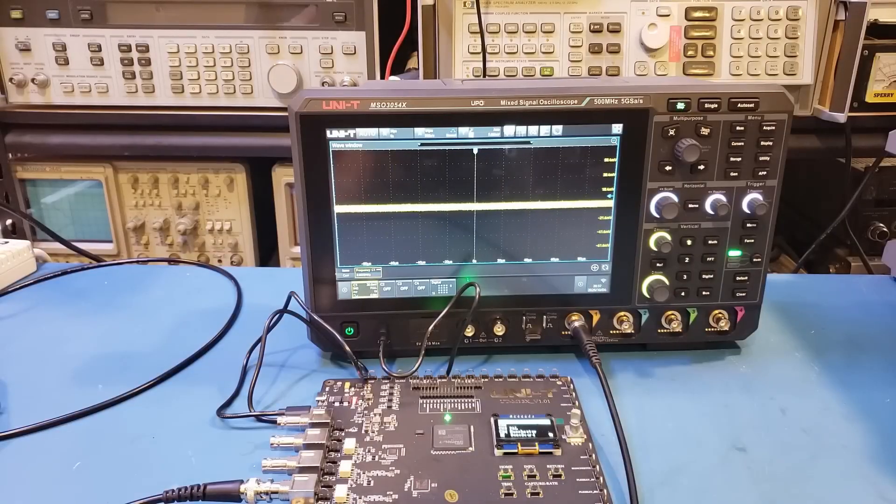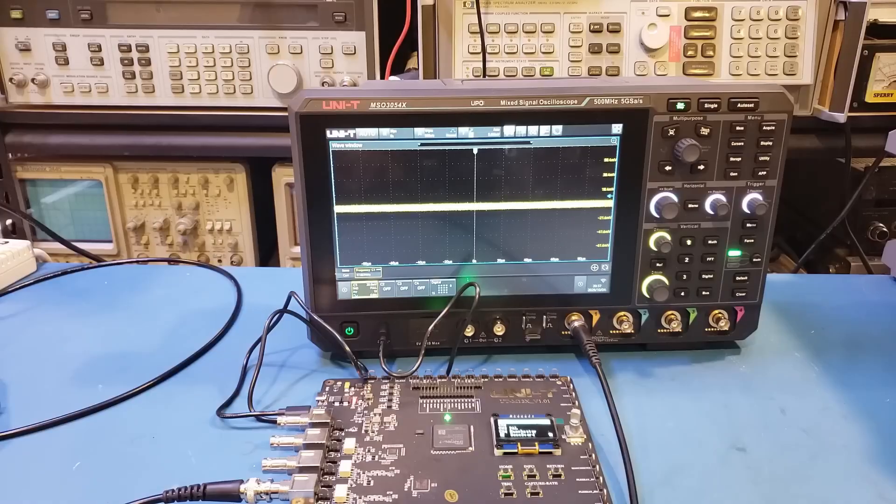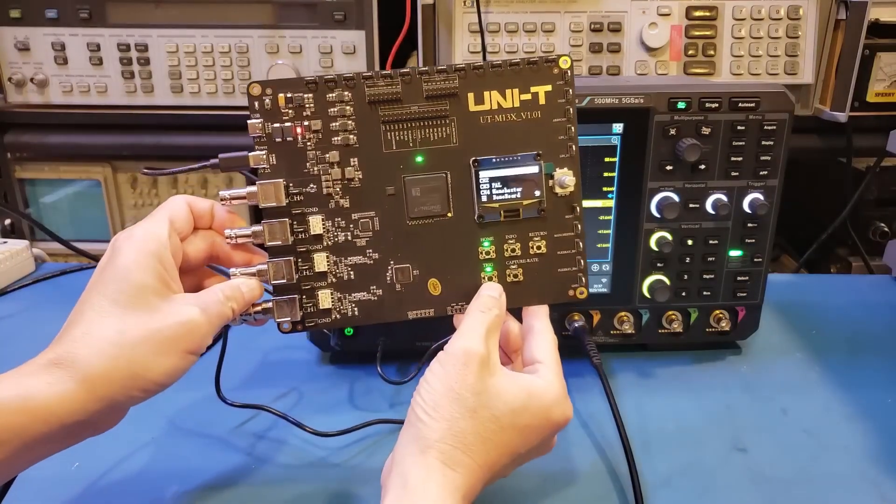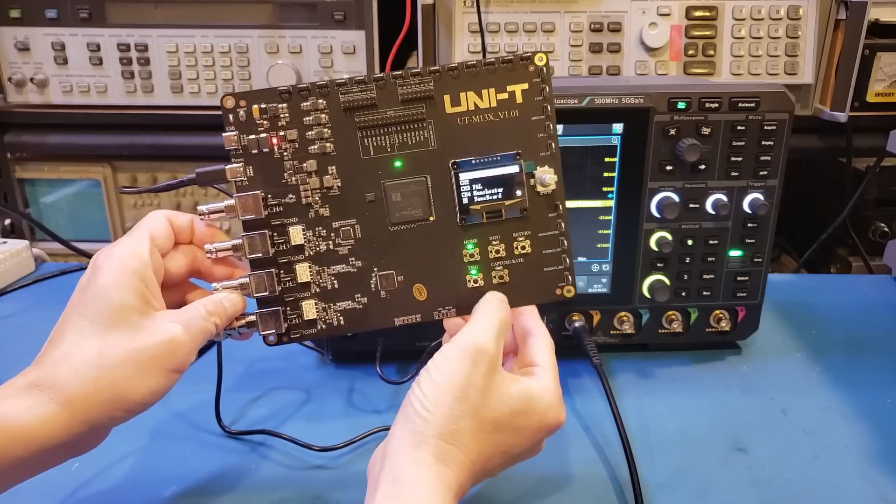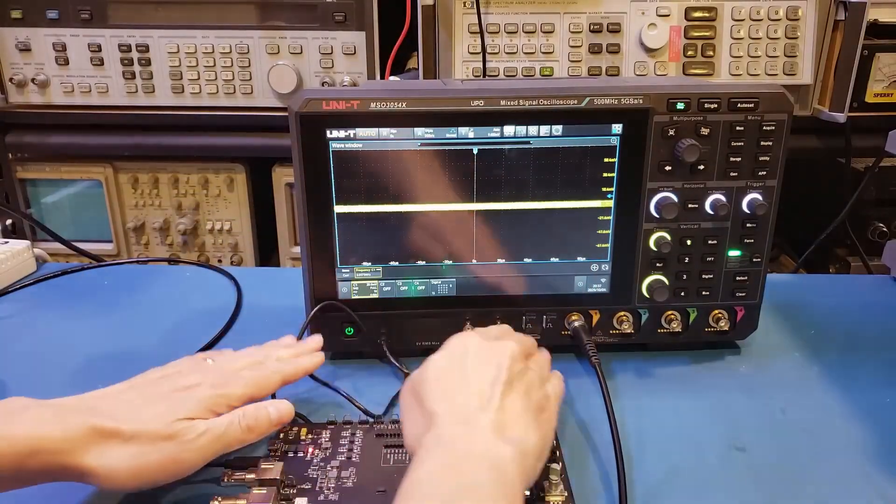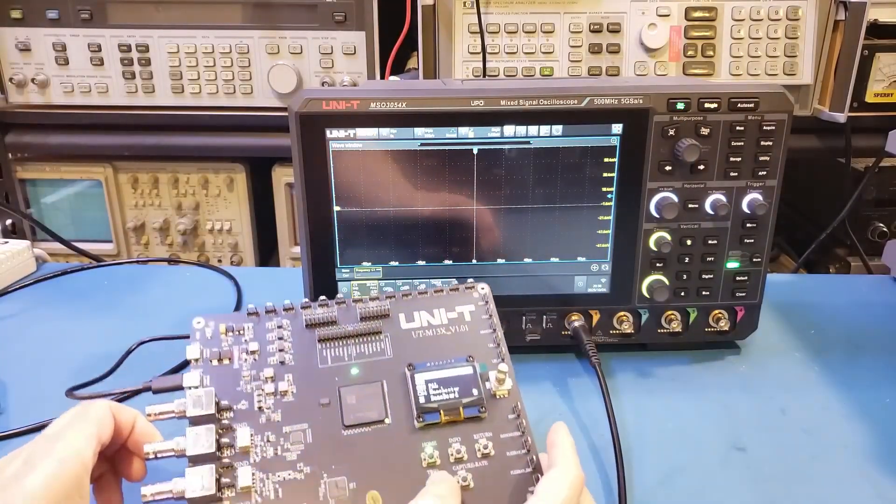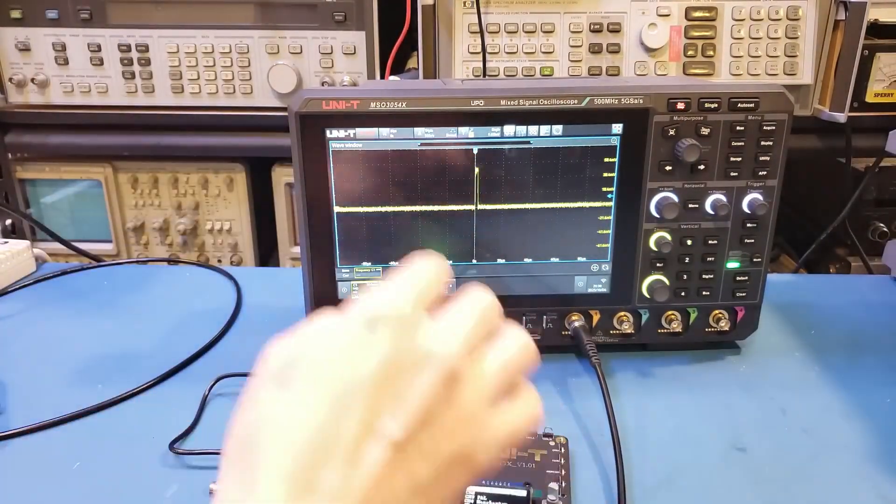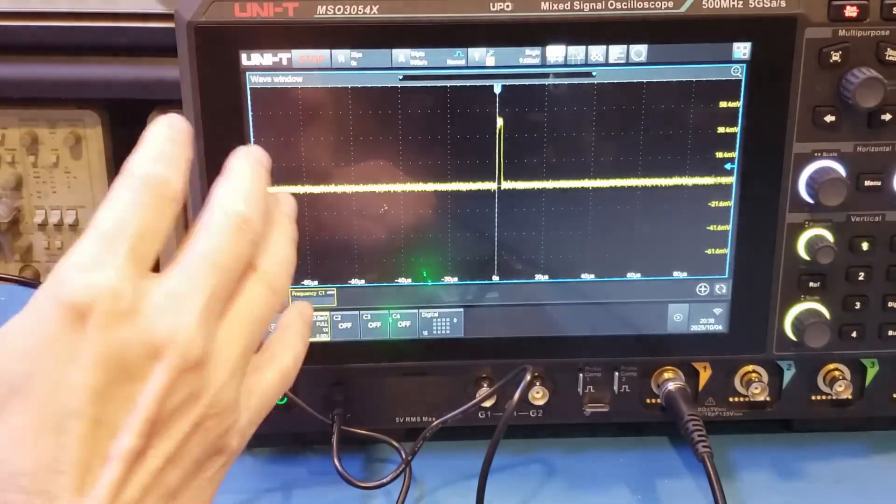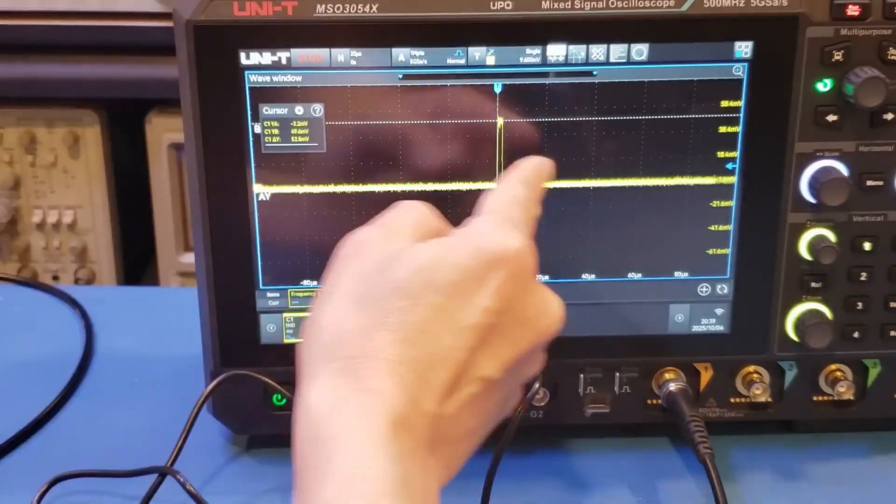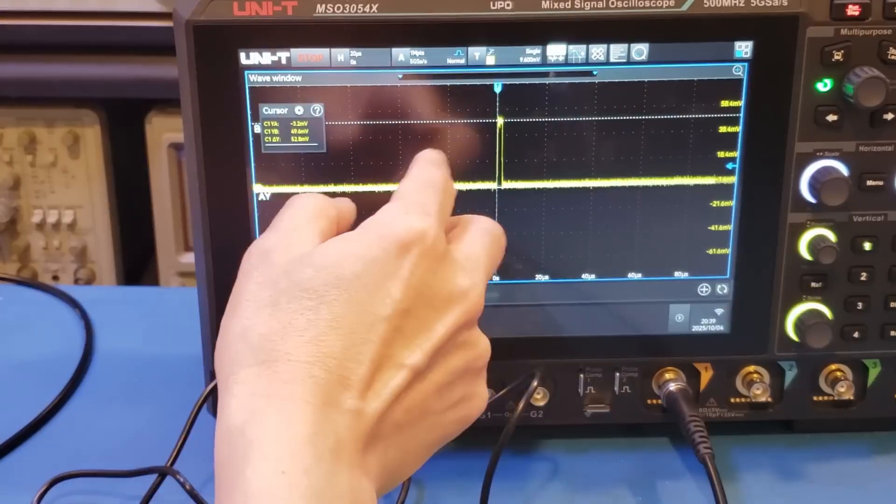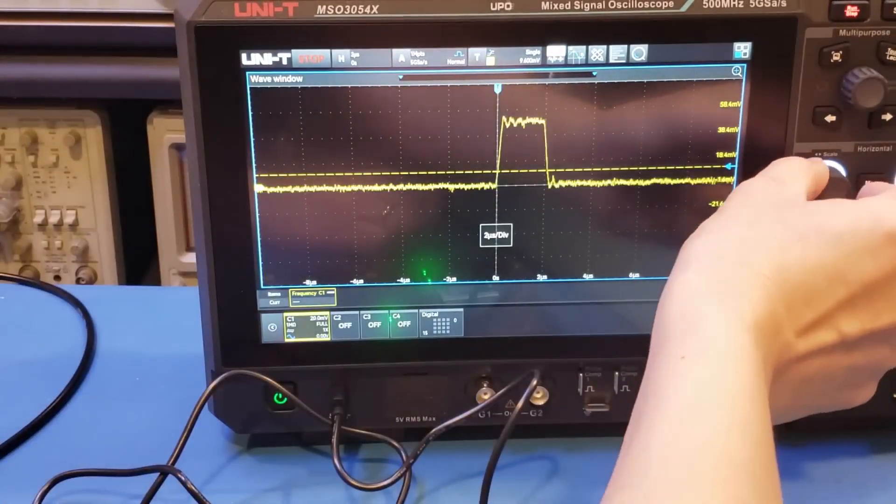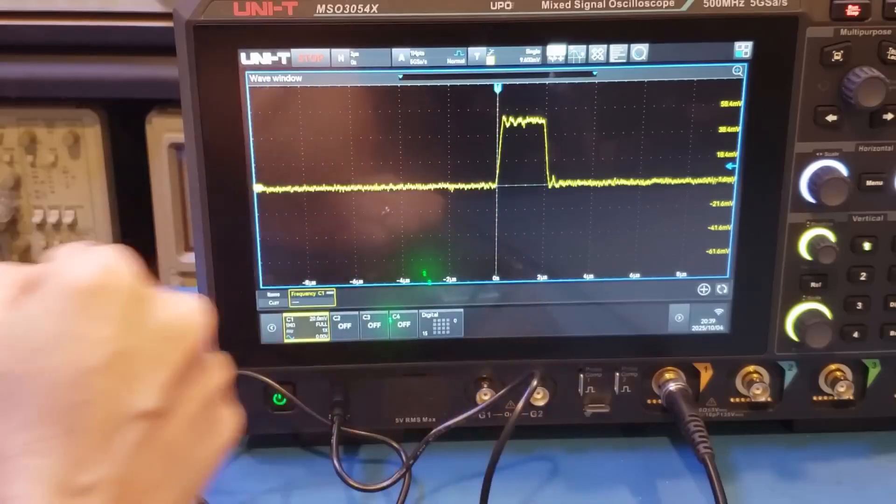The first complex one we're going to look at is a single short pulse. This one is useful for testing your single triggering capability. Once I have selected that, all I need to do is you can see here, now this trigger light is lit. So when I press the trigger, that will actually generate a single pulse. So let's take a look here. I'm setting my scope to single shot mode. And I'm going to trigger it. And you can see that we actually captured a single pulse. This pulse, because the amplitude is so low, it is actually not very easy for some oscilloscopes to trigger. You can see, the amplitude is roughly 50 millivolts. That's indeed a very small pulse signal. Now let's take a look at the duration. The duration is roughly 2 microseconds.